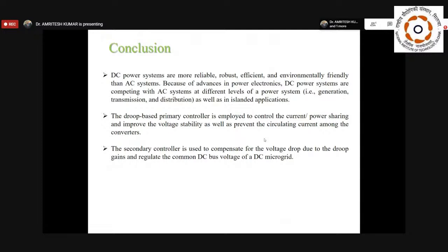Since reliability is higher, people are paying more attention to the creation of DC microgrids or DC homes. They try to satisfy the power requirement of the local community through DC power itself. So this is going to help a lot in the near future. We can apply this droop-based primary control with the secondary control, and it helps to improve the performance. How? By restoring the DC bus voltage to a reference voltage. Whatever demerits we have with the primary control can easily be tackled with the secondary control. Nowadays the primary control and secondary control are embedded in one control itself, working hand in hand, so they are not separate controls.